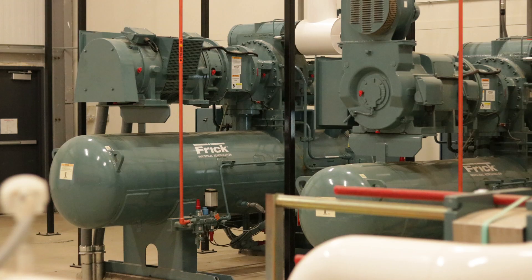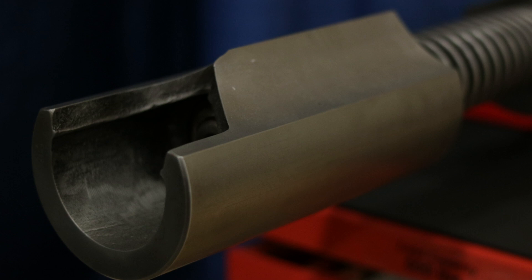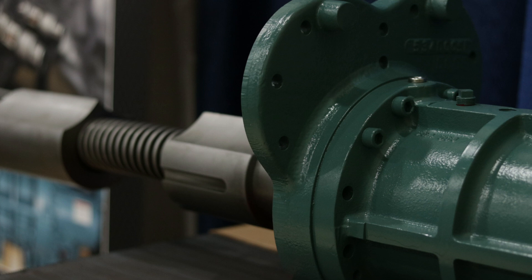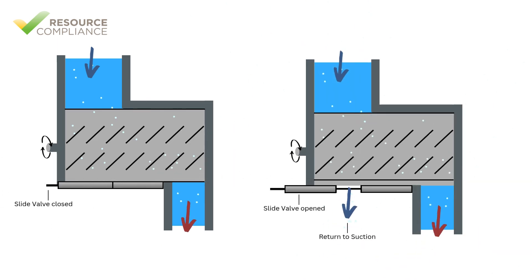In screw compressors, capacity control is typically achieved by employing what is called a slide valve. The slide valve is located between the rotors and consists of a sliding member that covers an opening that allows gas to be vented back to suction. During part load conditions, the slide will move to uncover the opening, which will decrease the amount of vapor that is compressed.